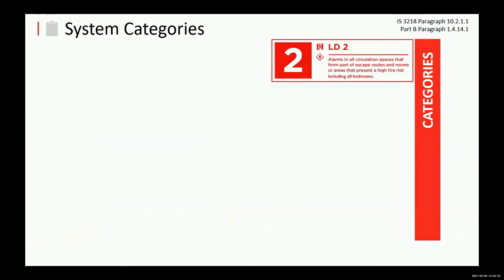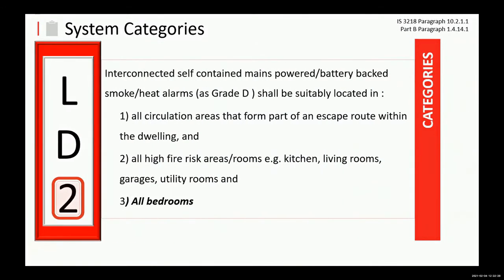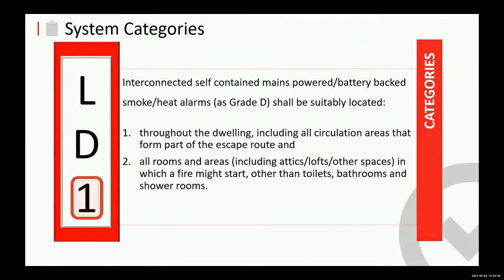So if we look at the system categories, then the minimum level of detection within Ireland at the minute is LD2. And again, we spoke about this earlier. It's in all circulation areas that form part of the escape route within the dwelling. It's in all high-risk areas like kitchens, living rooms, utility rooms, and all bedrooms. So that's the minimum level of detection within the residential premises. If we look at LD1, there's very little difference. Only any other rooms, I suppose, that haven't been covered, and that would include attics, lofts, and other spaces in which a fire might start, other than toilets, bathrooms, and shower rooms. Again, they're all grade D, and these are for new builds, major refurbs, and rewires.